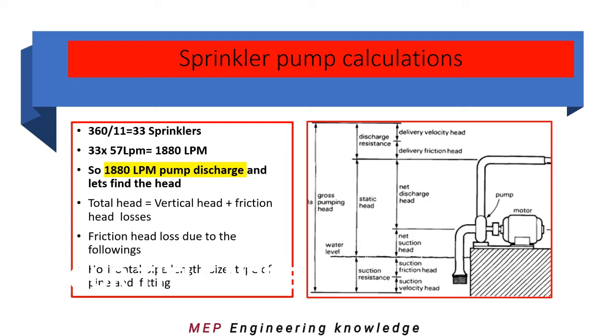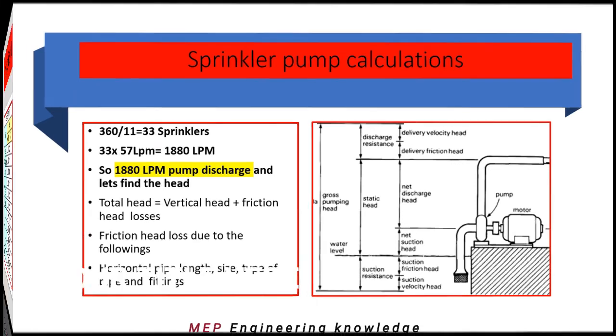Now let us find the head for the pump. The total head is the summation of vertical head and friction head losses. Vertical head is the vertical height of the pipe. Friction loss is arrived at by the summation of horizontal length, pipe size, pipe type, and fittings, by referring the chart attached here. Using the chart, we can convert the losses in fittings into equivalent pipe length, and thereby arrive at the total head easily.